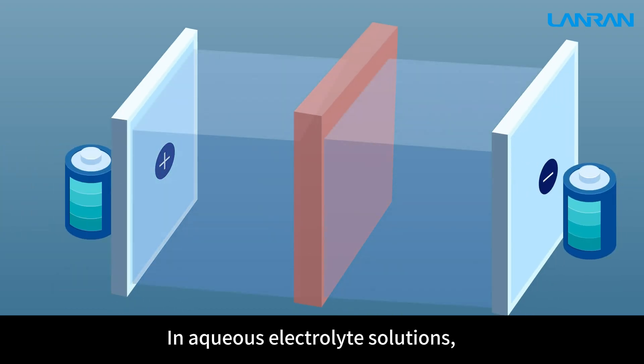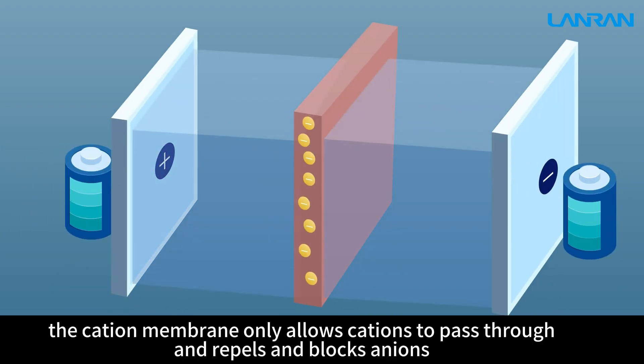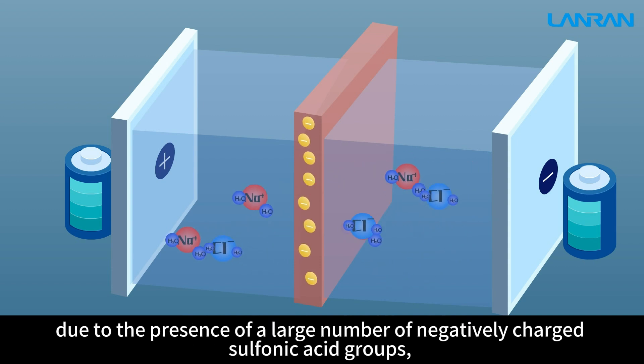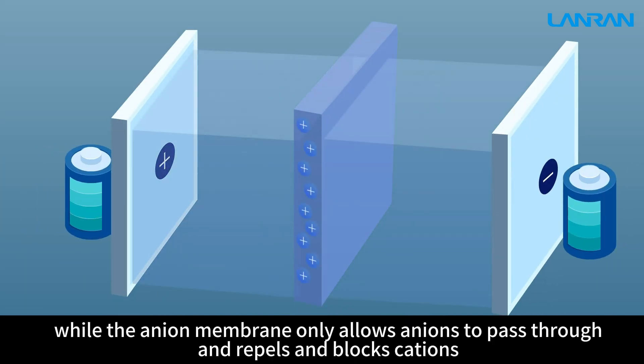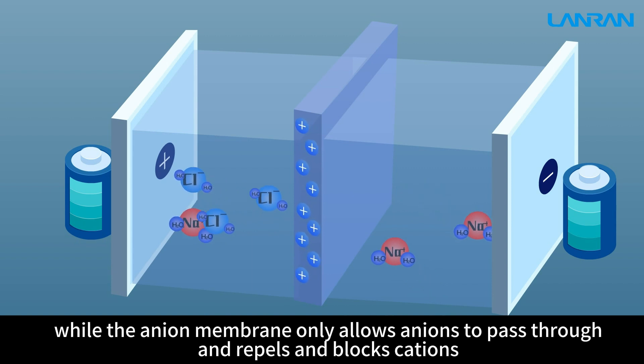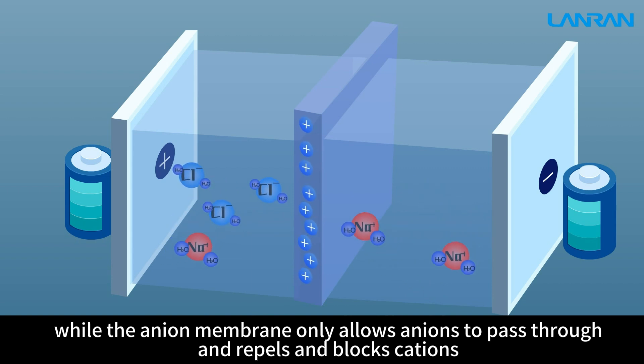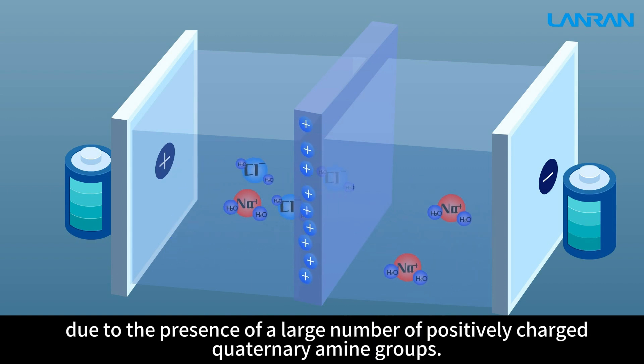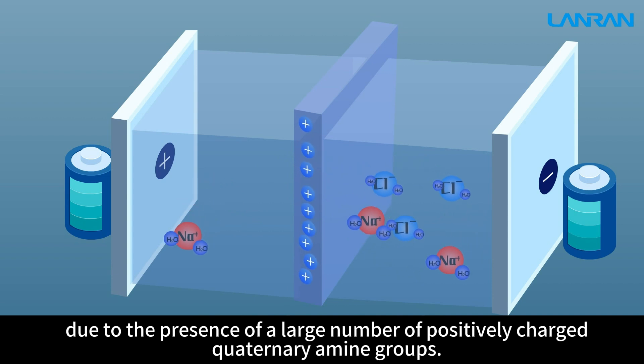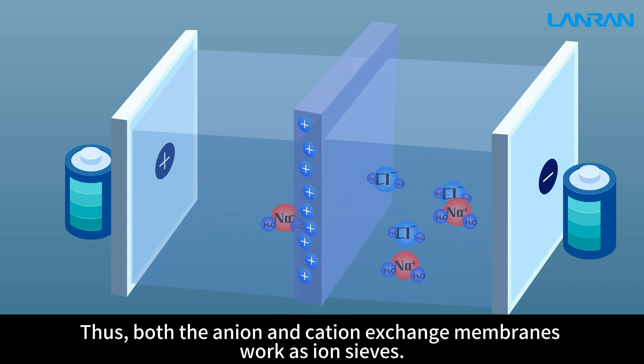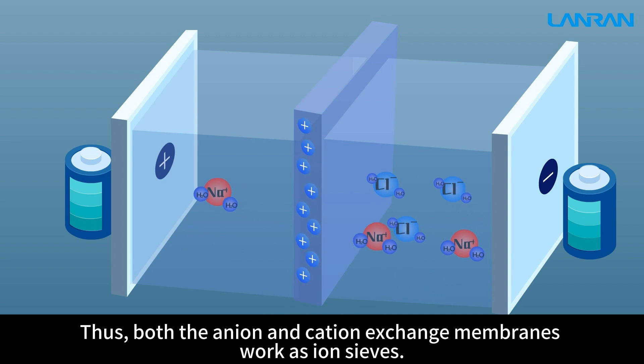In aqueous electrolyte solutions, the cation membrane only allows cations to pass through and repels and blocks anions due to the presence of a large number of negatively charged sulfonic acid groups, while the anion membrane only allows anions to pass through and repels and blocks cations due to the presence of a large number of positively charged quaternary amine groups. Thus, both the anion and cation exchange membranes work as ion sieves.